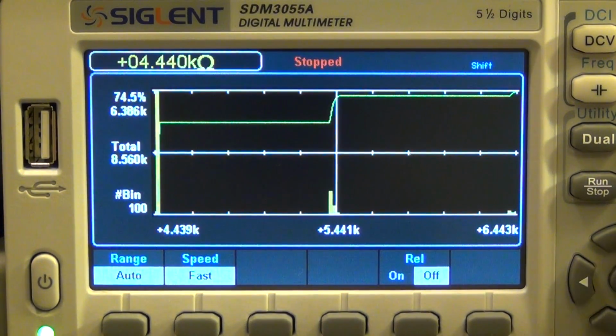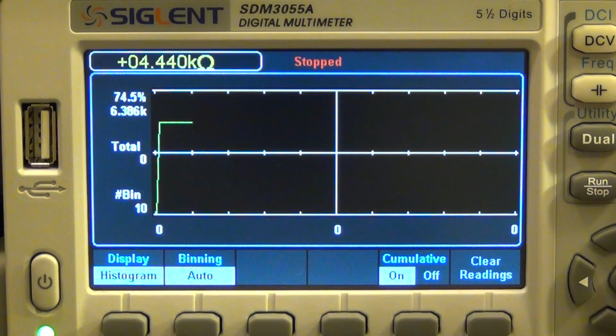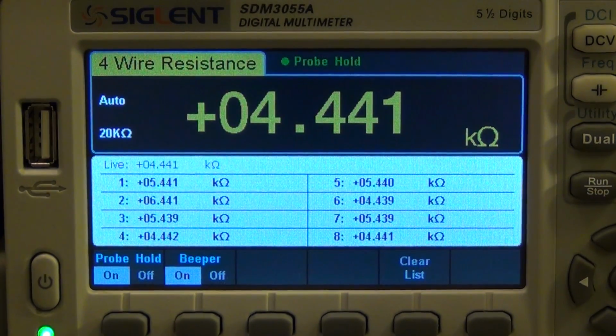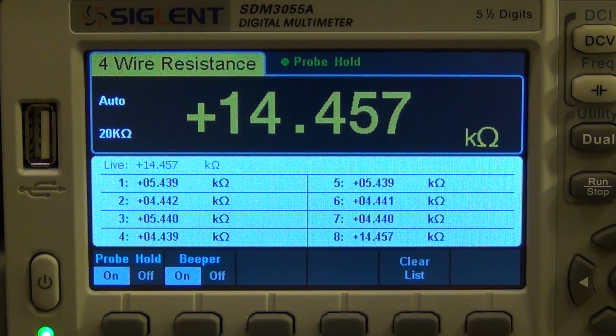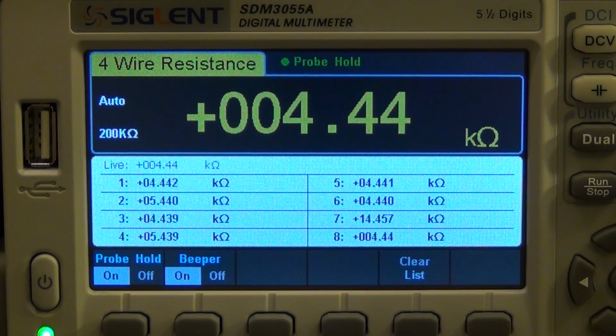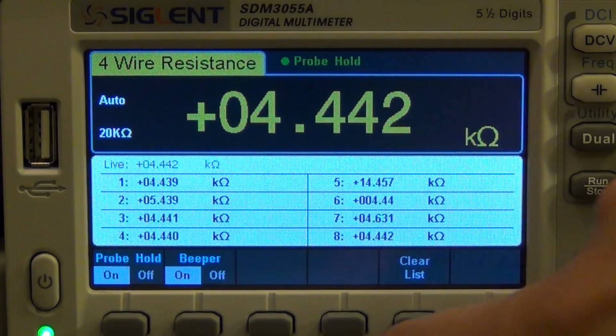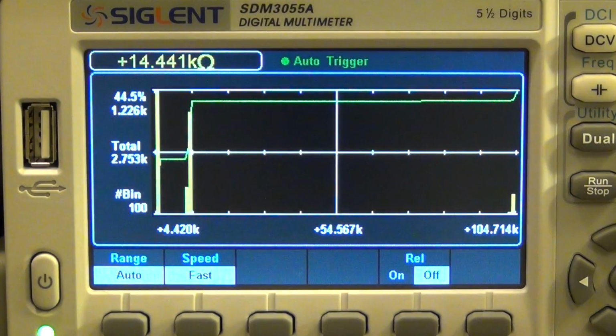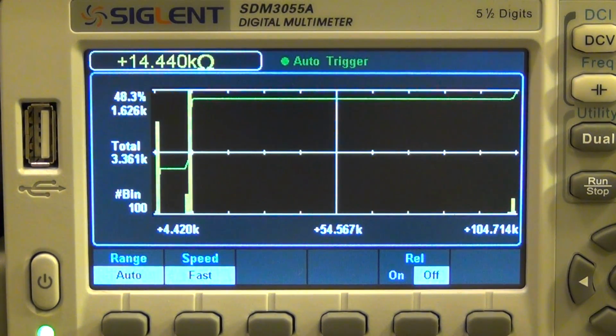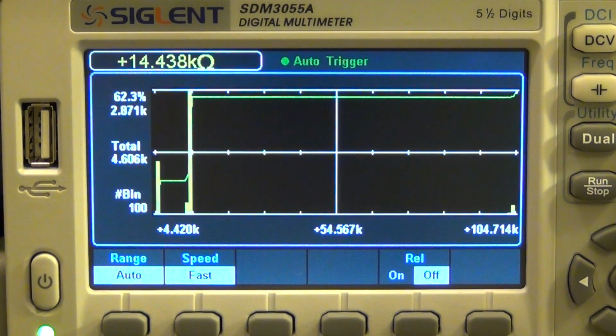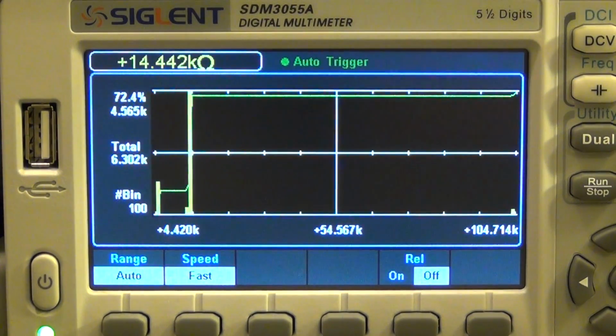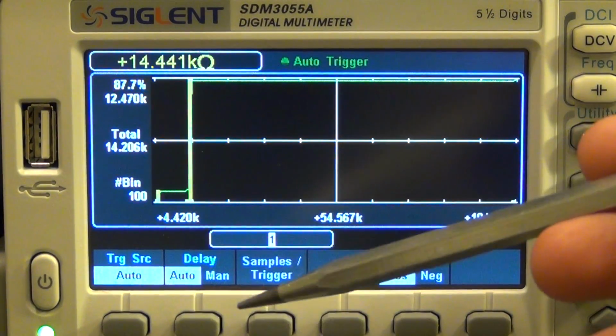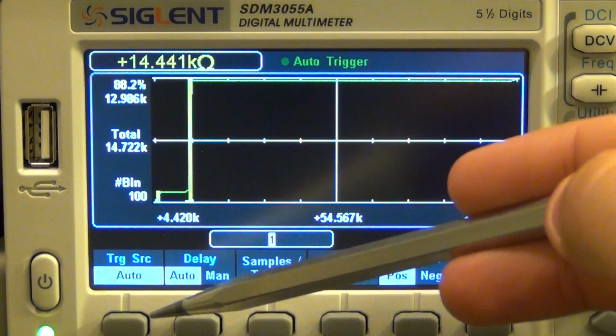But if I go ahead and clear this reading, and I go to hold mode here and take a couple of measurements like so, just a whole bunch of different measurements, and I go back and turn this off, you can see that it's built a lot more values than what I've actually measured. So anyhow, that's one little thing that I would have preferred if it was done a little bit differently, because as soon as you go back to this menu, of course you lose your histogram because it's making new measurements. That's one thing that can easily be added in software, and I hope that's something that they would consider.